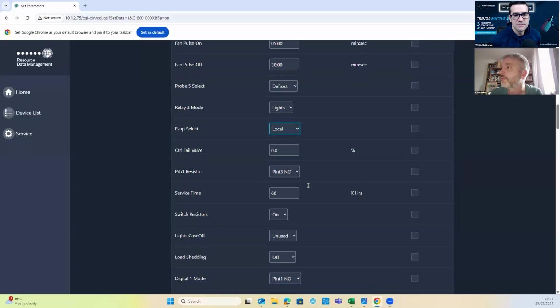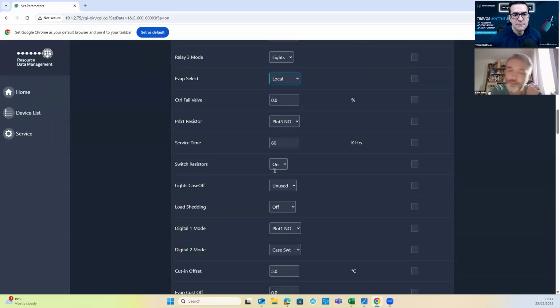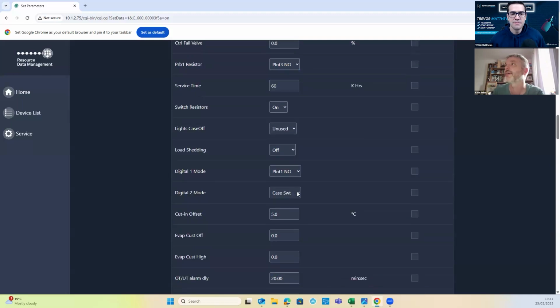Yeah, so if I do it, it's going to declare a transducer fault now because I've got a transducer wired into it. Switch resistors, that's the useful one. So you can tell the controller, by putting a resistor across some of the probes, to put itself into fans only, put itself into lights only. You can tell it to do a defrost. You can tell it to do lots of things with the resistor across the controller. Again, explained in the manual, but if you want that function, you need to turn it on. And then you will have the option, depending on where you put that resistor, to do different functions.